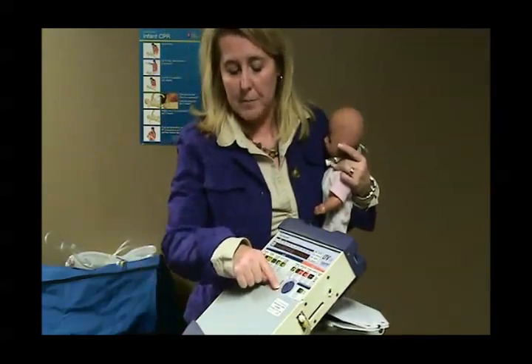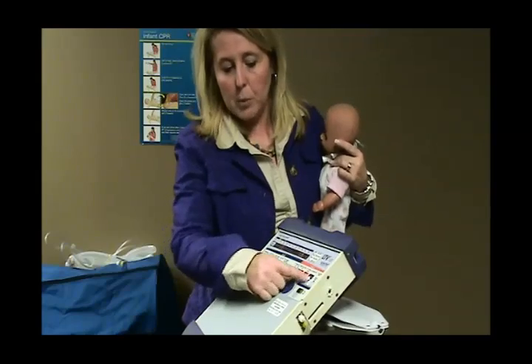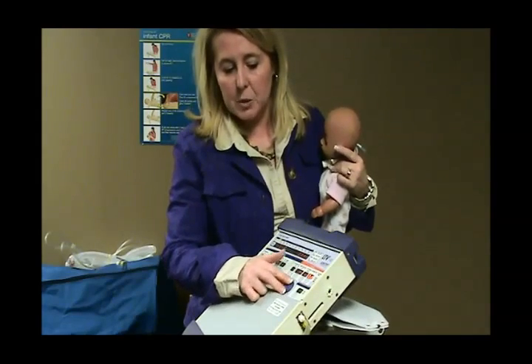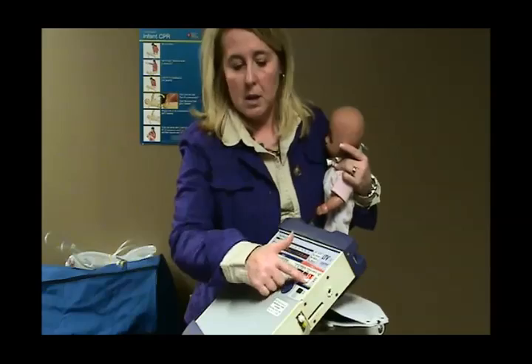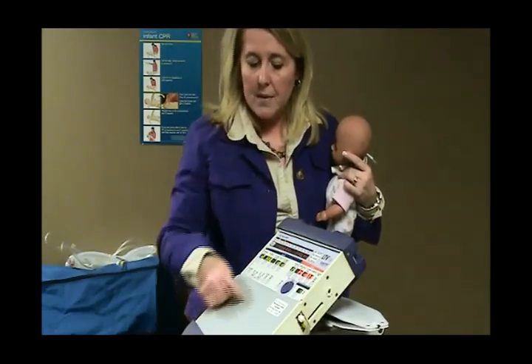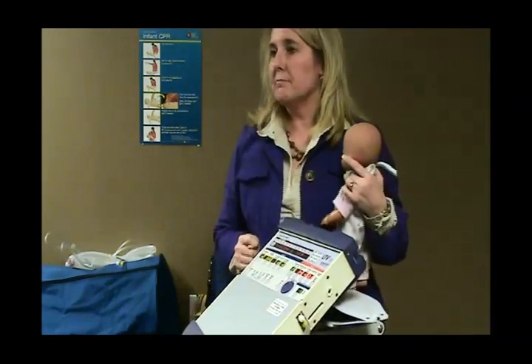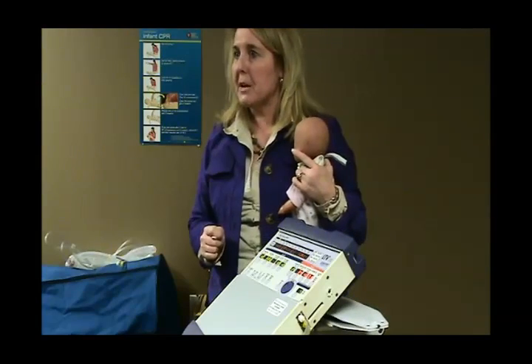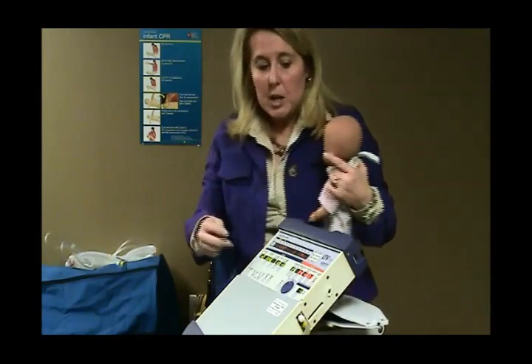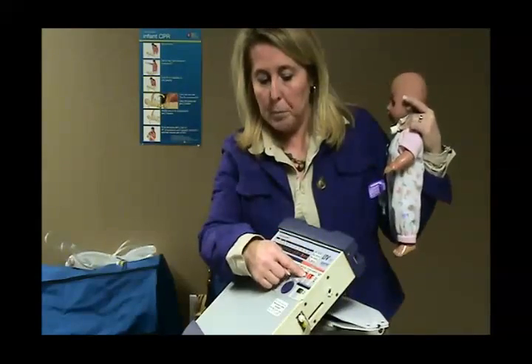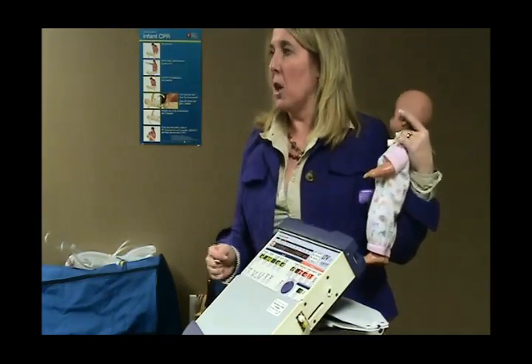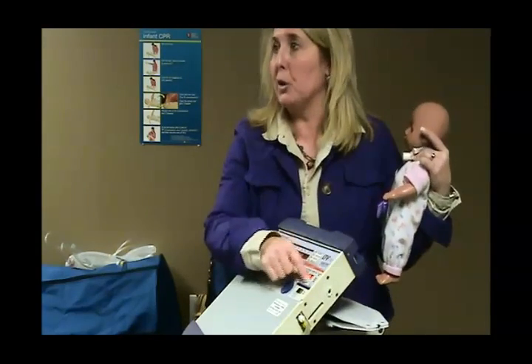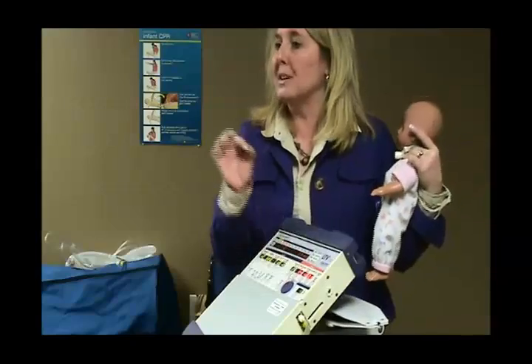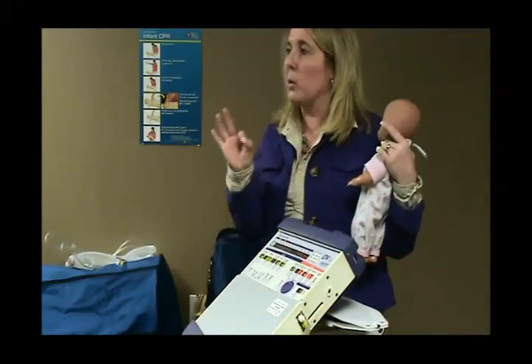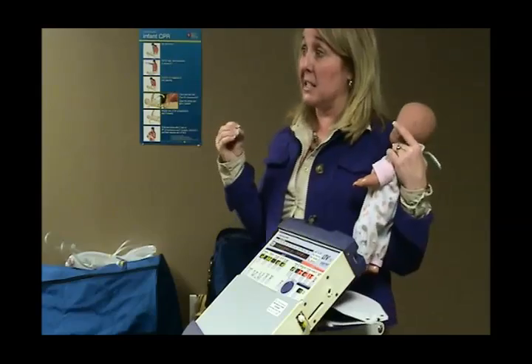Now we're going to unlock it. We're going to press it. We're going to turn it back to whatever it was supposed to be set on. And press it. And then we're going to relock the front of the ventilator. Okay? Sound good? Alright. So, your 2 disconnect alarms that you have on your ventilator are your low pressure and your low minute volume alarm. Okay? So when you disable your low minute volume alarm, your low pressure is now your only disconnect alarm. It's the only way for us to know if the patient is disconnected.